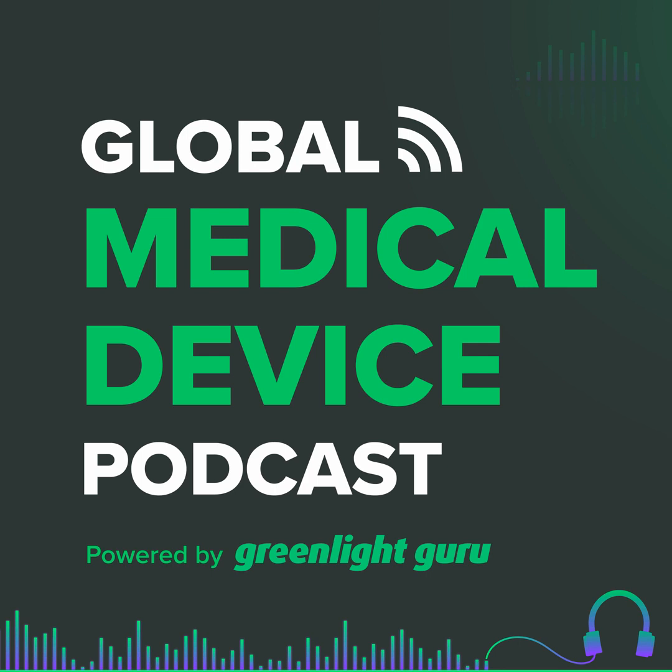One that I think is a great piece of advice is going to that FDA website and looking up your product code. Maybe we're talking about a class 2 device and you have a predicate in mind: look up that predicate and see the risks associated with it. That's a great piece of advice, though sometimes it's a little bit difficult to unearth for some newer companies. A lot of people don't know it's out there.